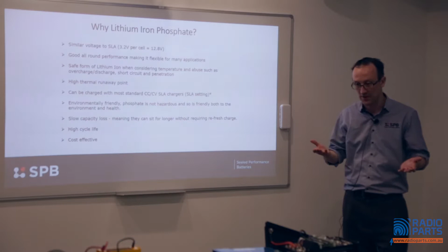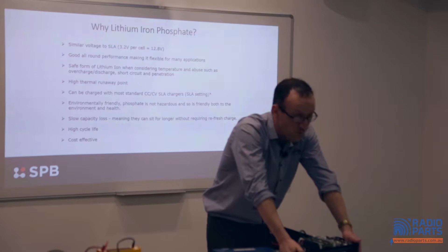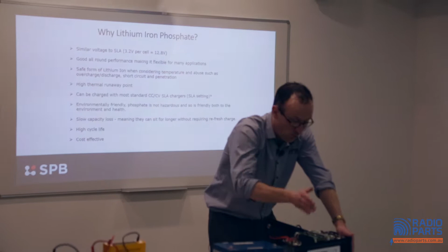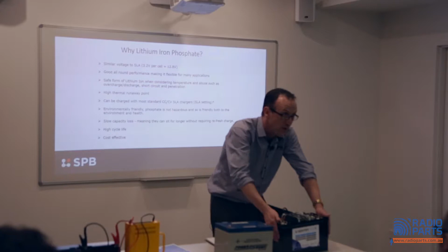And this is why I wanted to explain series parallel before, because there's only so much capacity you can get out of a cylinder or a wafer. So when lithium is loaded into an enclosure like this, it's loaded in a series parallel configuration. We're going to have 1, 2, 3, 4 in series to achieve that end voltage, but we've got to parallel up a whole bunch to achieve capacity.